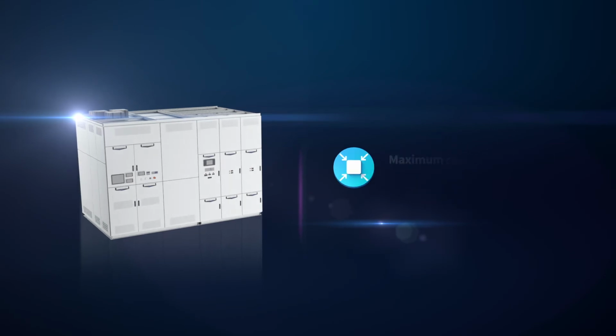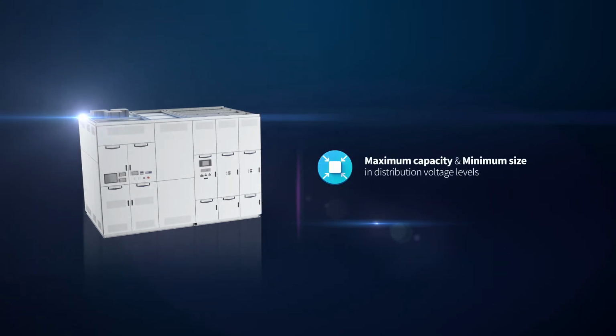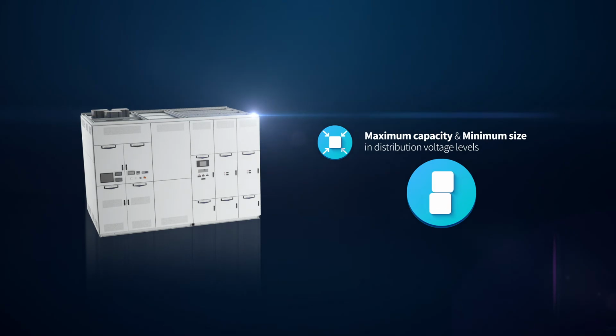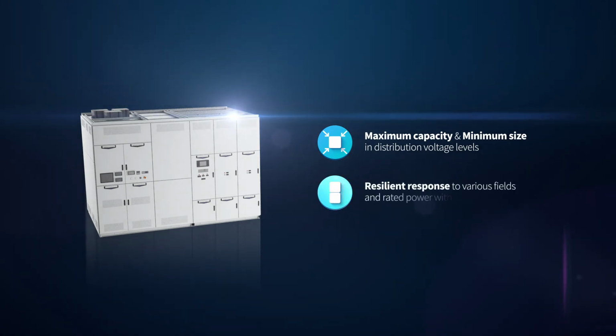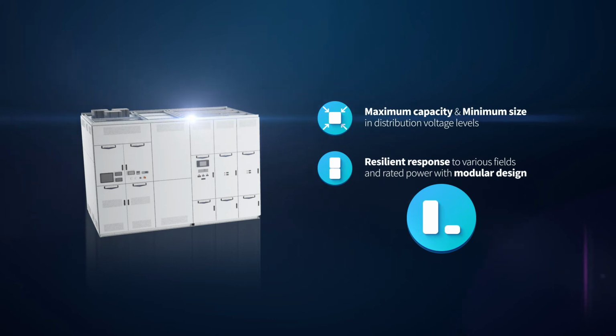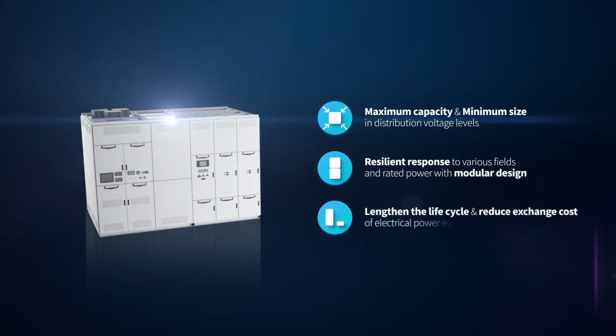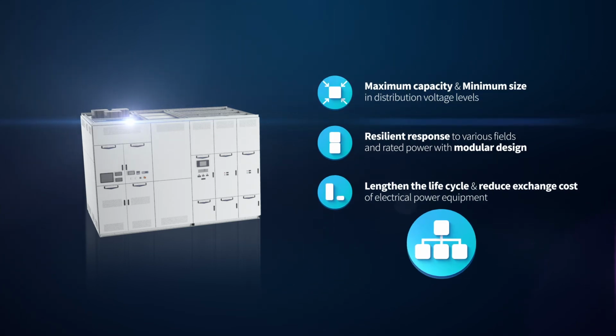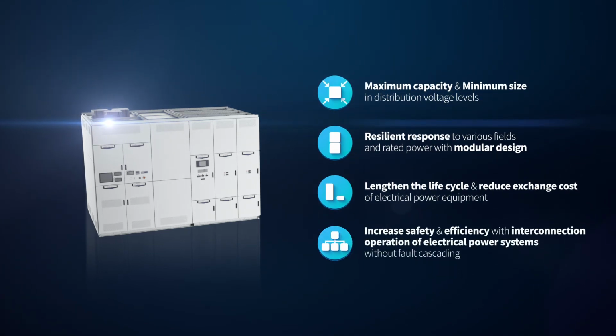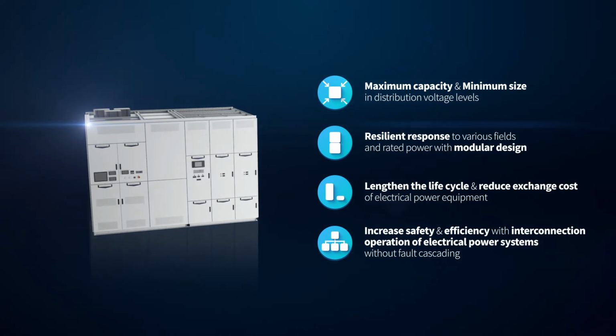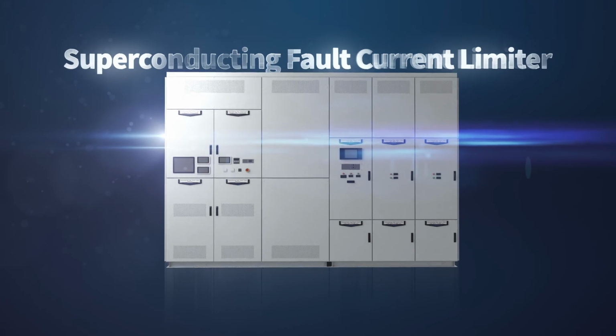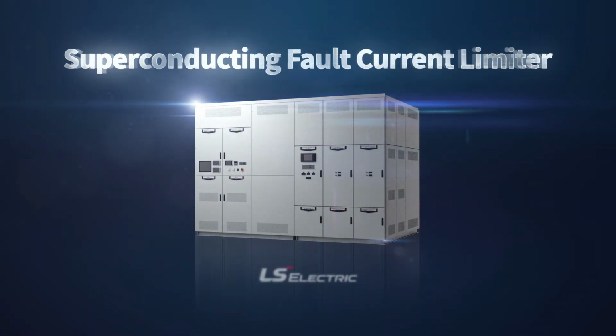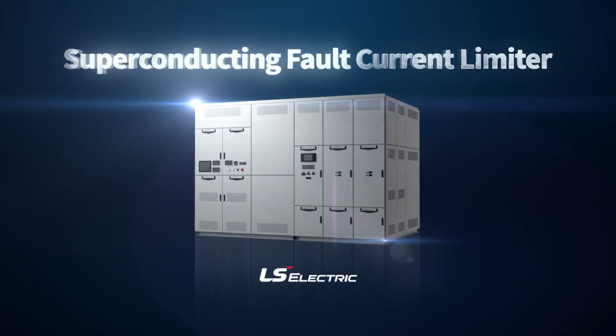Realize maximum capacity and minimum size in distribution voltage levels. Resilient response to various fields and rated power with modular design. Realize economic feasibility by increasing the life cycle and saving exchange costs of electrical power equipment. Increase safety and efficiency with interconnection operation of electrical power systems without fault cascading. LS Electric presents Superconducting Fault Current Limiter, which accumulates all of these.